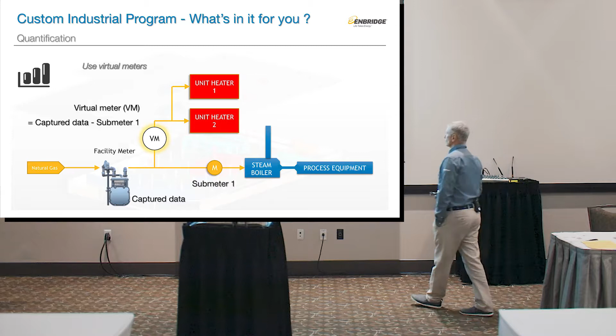It's just a matter of calculation, used in conjunction with other metering methodologies, typically from the utility meter. Somebody captures data from the utility meter, uses that as a total, then subtracts some other meter—like the steam boiler example—to get the virtual meter values. That's all it is. So in that example, we'd have captured data, a meter on the steam boiler, and we'd subtract the two to get the virtual meter data on the unit heaters. Simple as that—you only have the cost of the sub-meter and of capturing the data.